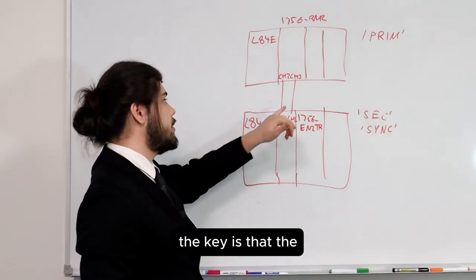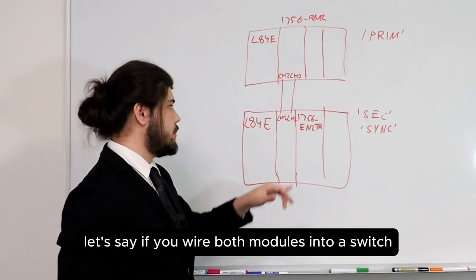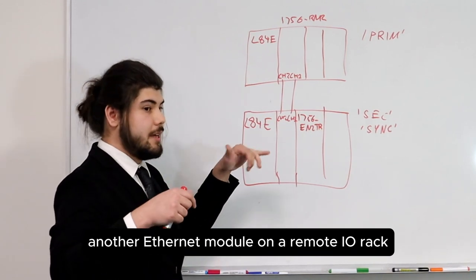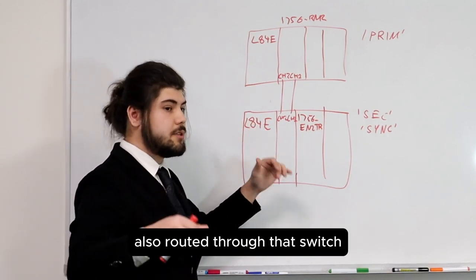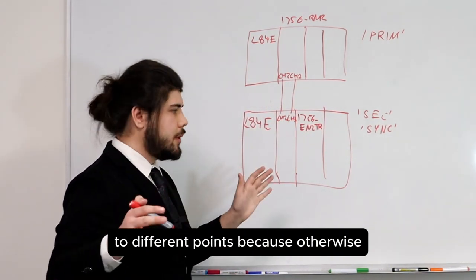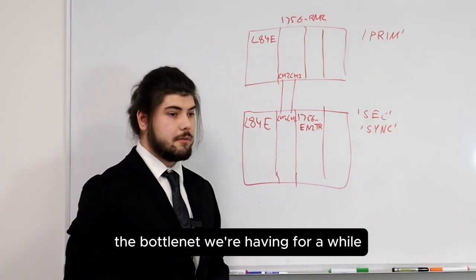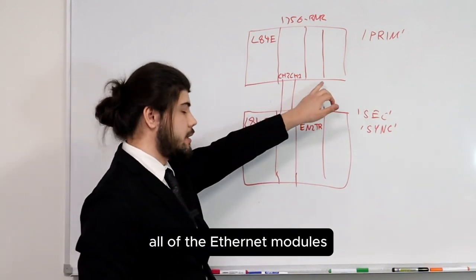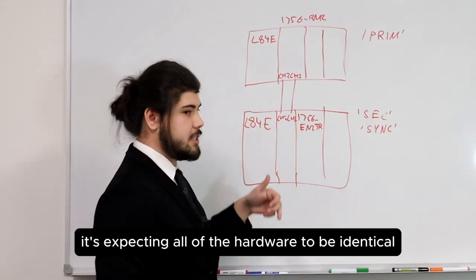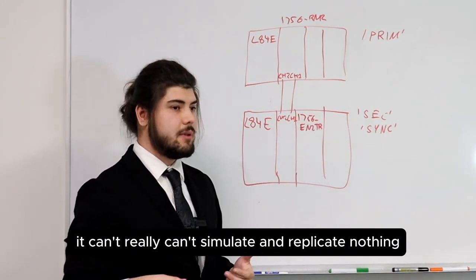The key is that communication modules in the same slot must be able to communicate over that network. If you wire both modules into a switch, then both modules can communicate through another Ethernet module on a remote IO rack, also routed through that switch, and maintain connection through switchover. You can't have the same-slot Ethernet modules communicating to different points, because otherwise they can't communicate with the same device — in our case our remote IO rack. This was actually the bottleneck we were having for a while, because we didn't realize that all of the Ethernet module ports had to be used.